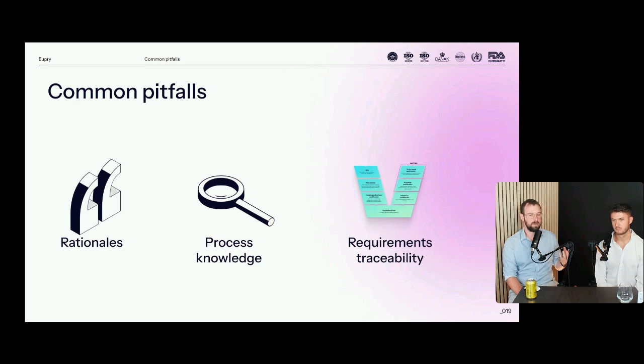And that's everything from what temperature span it should be, what's our acceptance criteria, the most basic, but also how much do we plan to move in and out, so that during design of the areas, you can actually get a design qualification, or at least a subject matter expert to verify that your design of your facilities will hold those requirements. And then linking those to how you perform your mapping.